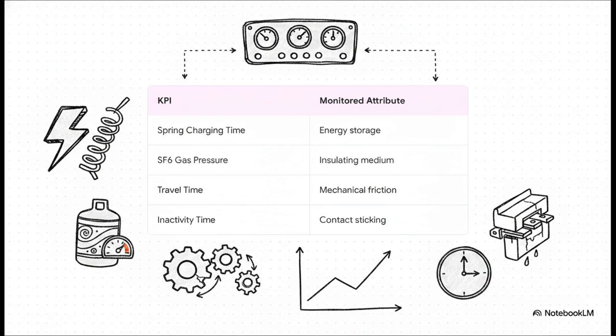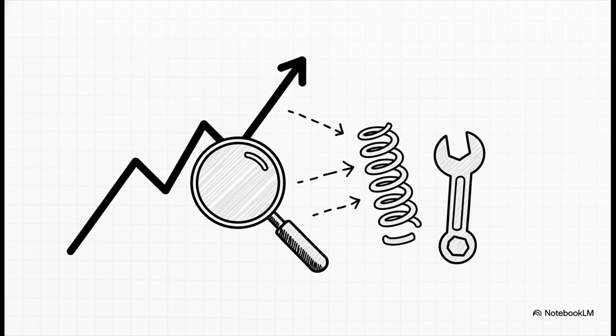Tracking spring charging time tells you right away if the energy storage mechanism is starting to degrade. Tracking SF6 gas pressure is critical for safely quenching an arc. Monitoring travel time helps you catch mechanical friction, but pay special attention to inactivity time. Seriously, a breaker sitting completely idle for months is a massive risk factor because lubricants dry out and sticky mechanisms develop from pure disuse.